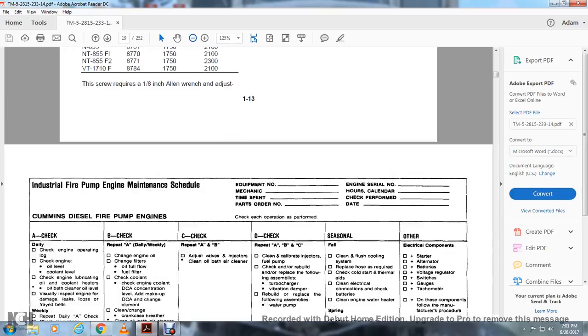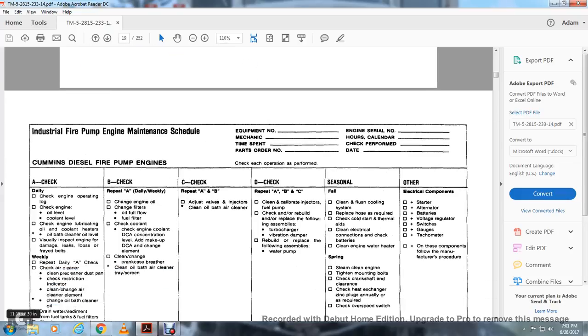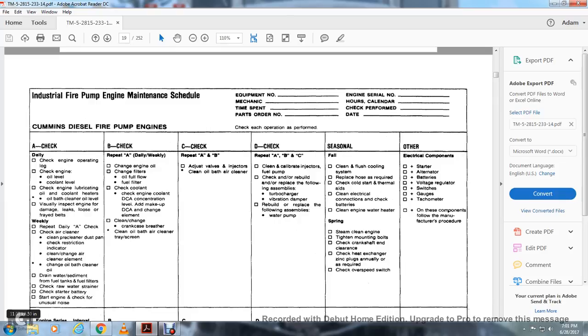All right, the industrial fire pump engine maintenance schedule: equipment number, mechanic, time spent, parts ordered, engine serial number, hours, calendar, and check performance date. Cummins diesel fire pump engine, check daily: check the engine operating, check the oil level and coolant, check the engine lubricating oil and coolant heater, oil bath cleaner and oil level. Visually inspect the engine for damage, leaks, and loose or frayed belts. Repeat the daily check of the air cleaner, clean the precleaner dust pan, check the restriction indicator, and clean or change the air cleaner element. Change the oil bath cleaner oil. Drain water and sediment from the fuel tanks and fuel filters.